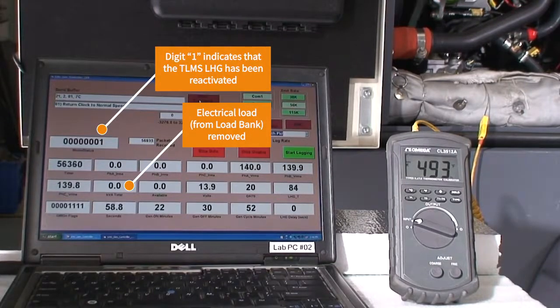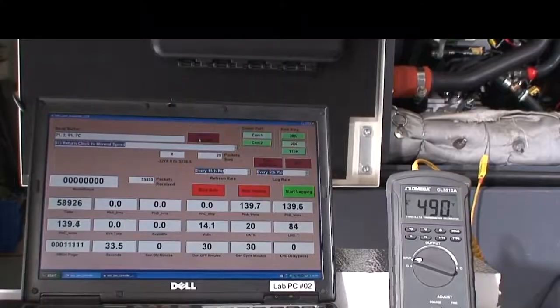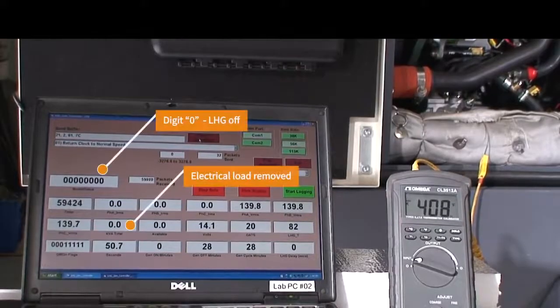If we now deactivate the LHG and leave the load bank turned off, the engine is now unloaded and the exhaust gas temperature rapidly reduces back down to about 338 degrees Fahrenheit. This is indicative of what happens when a diesel generator is operated unloaded. Please note that this portion of the video has been sped up to minimize the viewing time.